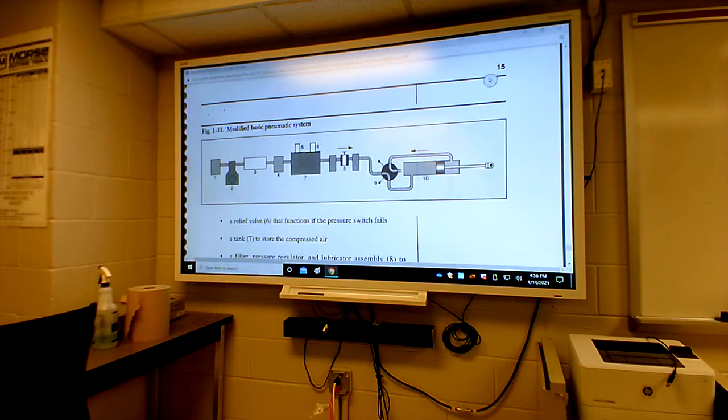I've done it myself. You go to a machine that the oil has been drying for so long that we forgot to put oil in, and the seals are getting dry. So we go over there and put oil in it. We cut it on, and then we say, "Well, I'm gonna ease up that oil drip rate a little bit and get everything lubricated kind of quick." And then you forget to go back and turn it down. It saturates the lines, and it starts puffing through the exhaust, and it's an oil mist that comes out, poof, and it's just oil in the air, poof. That girl said, "I need an operator to the lower rotary. My machine is smoking."